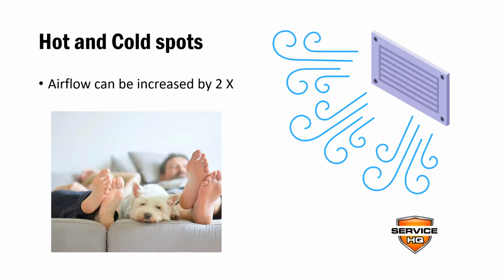Okay. Also, hot and cold spots. So, keeping a clean system, making sure that the airflow is what it needs to be. Airflow can literally be increased by 2 times. And one thing that I'll share with you about airflow, because I want to make this presentation as educational as possible, so you learn a few things, so it's worth your time, is that anytime you have a hot or cold spot, 9 times out of 10, you've got a duct issue. It's not necessarily because of the system. It can be some of that, but most of the time you've got a duct issue. You've got usually insufficient airflow to a particular room because there's not enough air being dumped into that room.